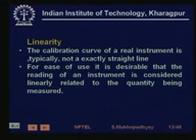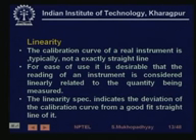So when you are telling the user to use the approximate model of the line for simplicity, you also have to tell them what kind of error they can expect if they use the linear model of the instrument. So that is given by the measure of linearity. The linearity specification indicates the deviation of the calibration curve from a good fit straight line.